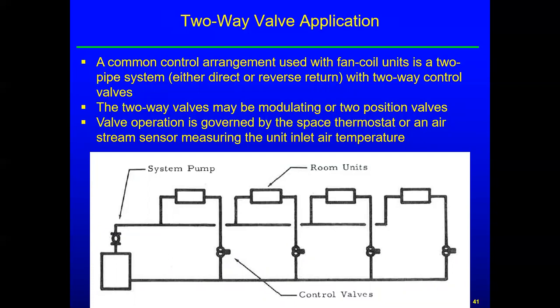And then the space temperature would have some sort of a band from, you know, a high, the high end of the band. When the temperature got to that point, it would shut the valve completely off, so you got no heat, and then it would let the temperature drift down to the lower end of the control band, at which point the valve would open.